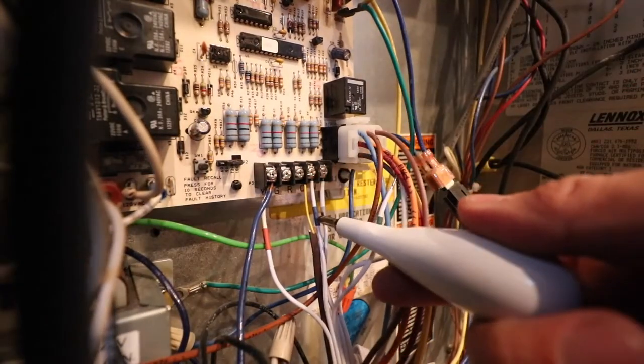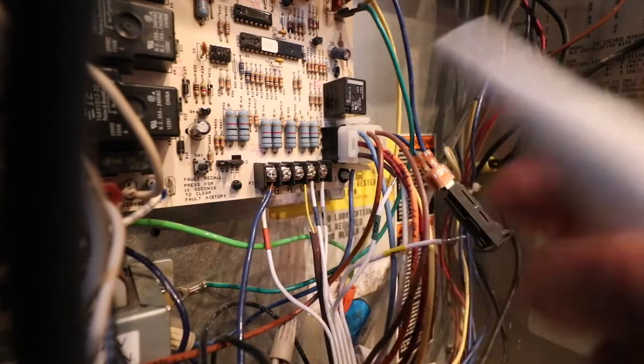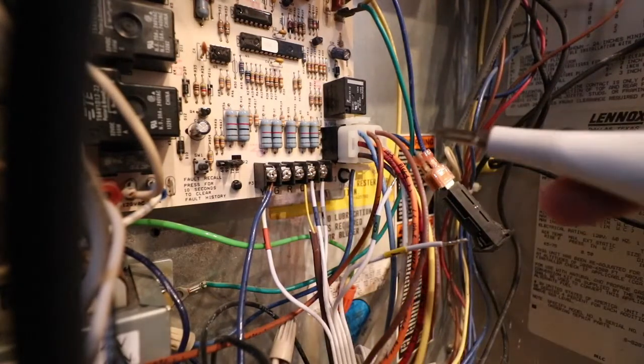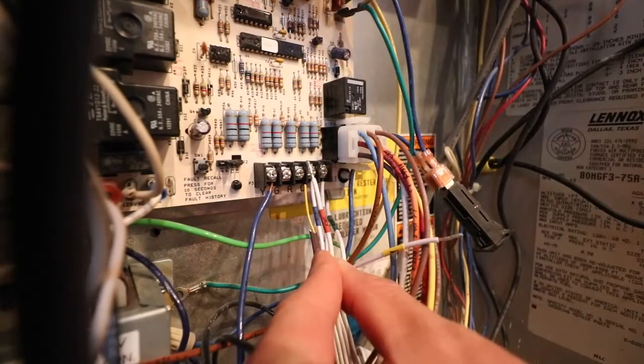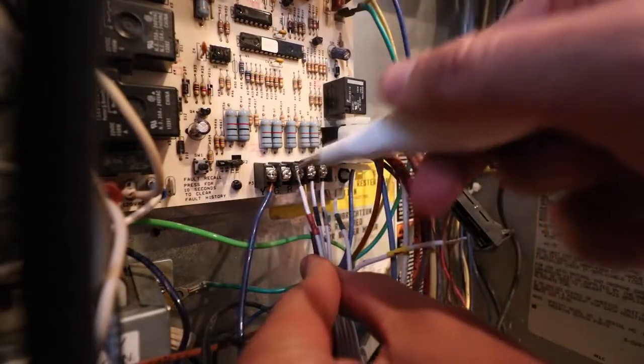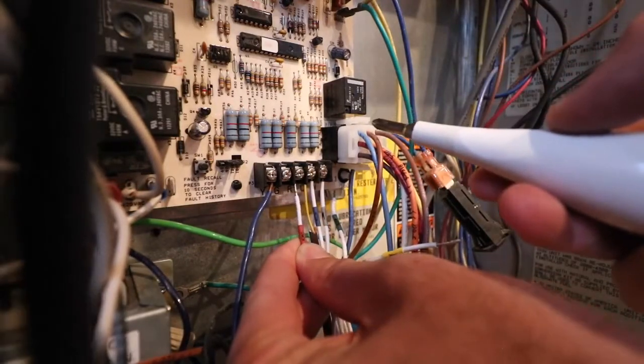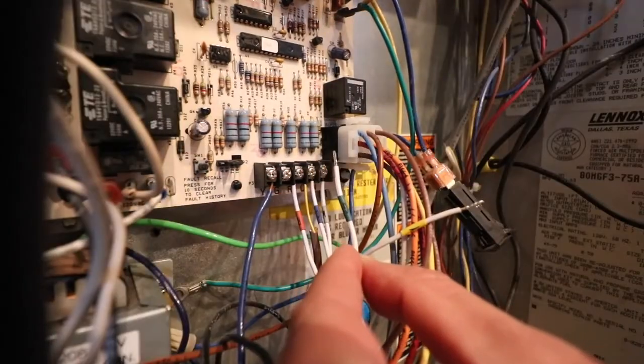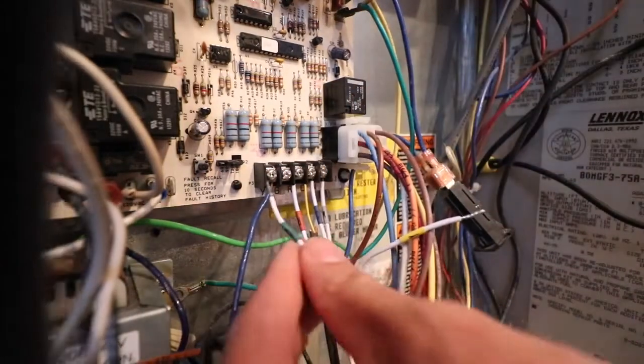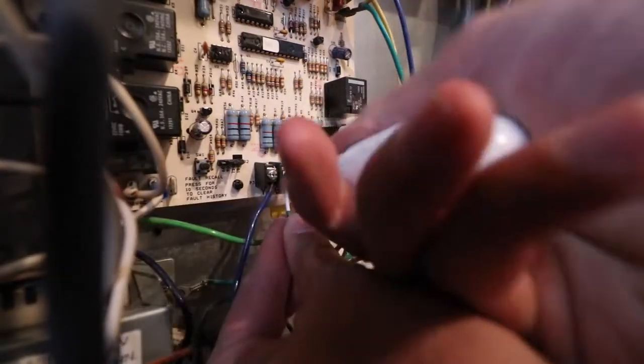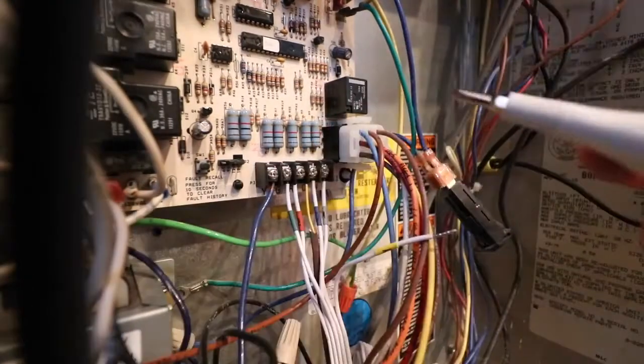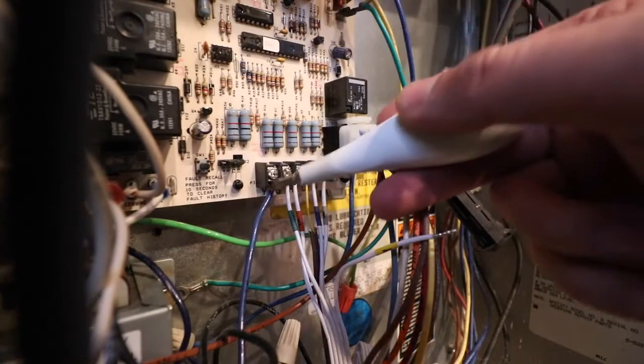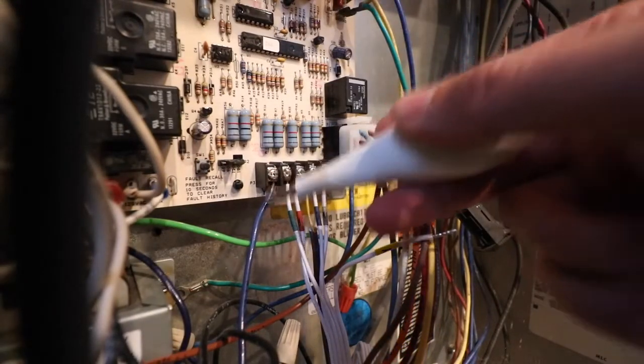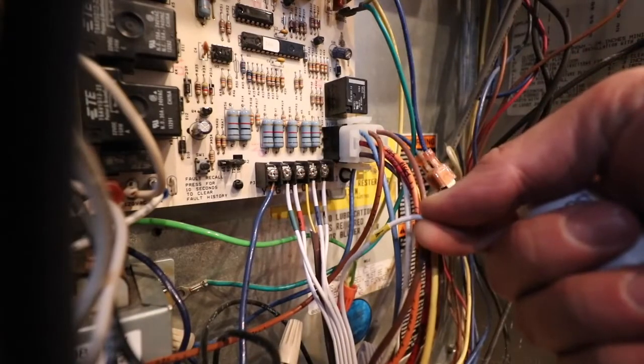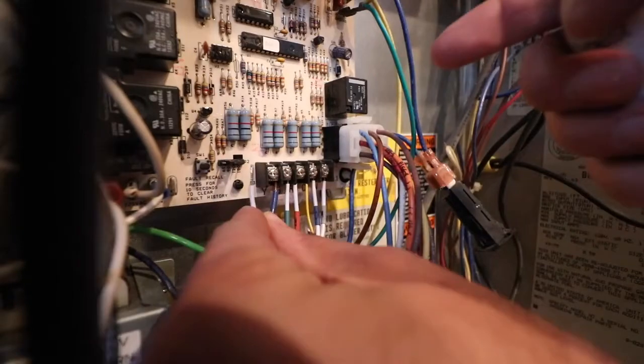Now we have the C wire connected and the existing yellow wire that was connected to the C terminal. If we had more wires, we'd also want to leave those connected as well. Now we take our R wire and we connect it to the R terminal on the control board. Now we take our G wire and connect it to the G terminal on the control board. Now we're down to our last connection, and we have our existing wire on the Y terminal, which is going to remain, and we're going to connect our Y wire from the adapter into the control board as well.